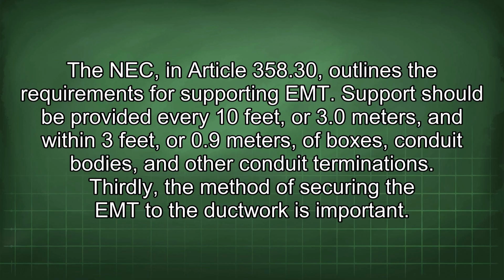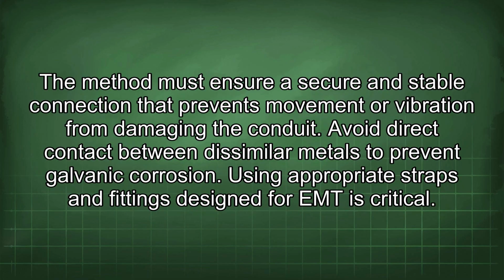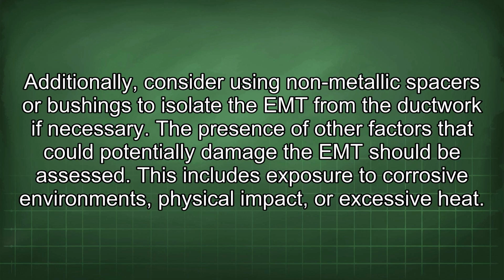Thirdly, the method of securing the EMT to the ductwork is important. The method must ensure a secure and stable connection that prevents movement or vibration from damaging the conduit. Avoid direct contact between dissimilar metals to prevent galvanic corrosion. Using appropriate straps and fittings designed for EMT is critical. Additionally, consider using non-metallic spacers or bushings to isolate the EMT from the ductwork if necessary.